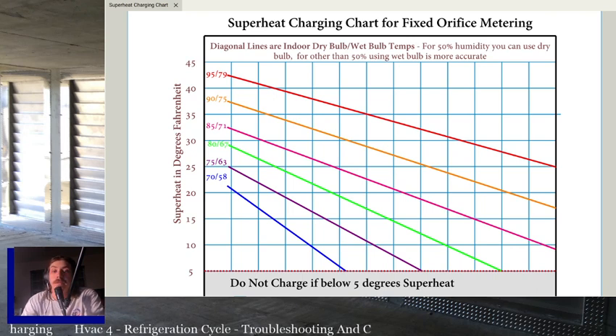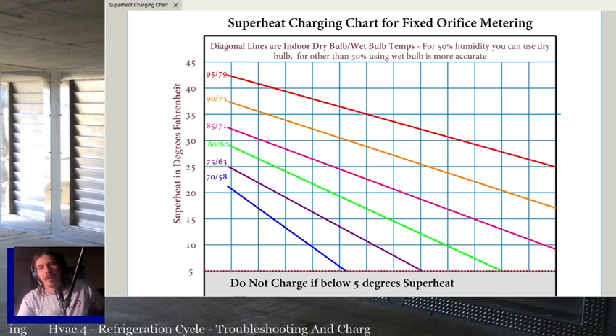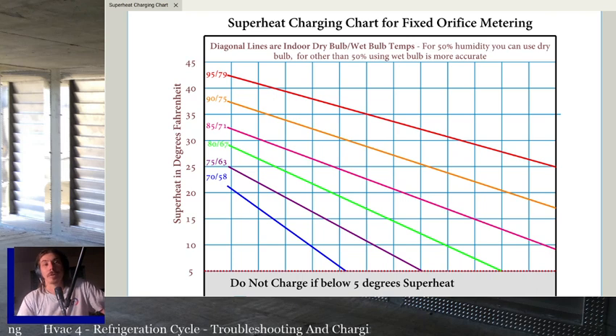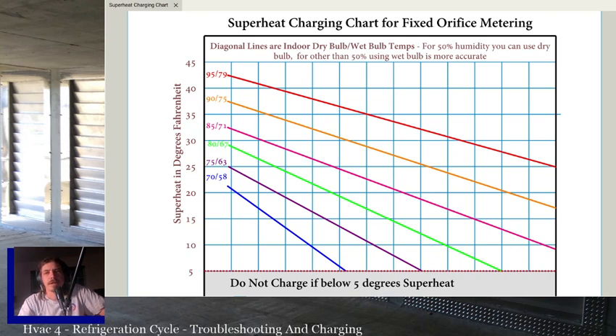the first thing you want to do is make sure everything looks clean and it looks like your charge is good, at least halfway. Obviously, if you've got an undercharge, that's part of what we're going to talk about. But you want to make sure everything looks clean. You don't want to be troubleshooting refrigeration issues and have a problem on top of a dirty coil. We'll talk about what dirty coils look like. If you look at the coils, the fan wheel, or the filter, and that stuff's dirty, you don't want to keep trying to find a problem when you've got other things. You want to narrow it down to one issue in the refrigeration circuit that you need to figure out. If you're trying to troubleshoot it on top of those things, you're just going to have a bad day.